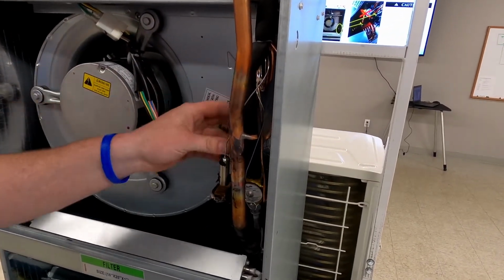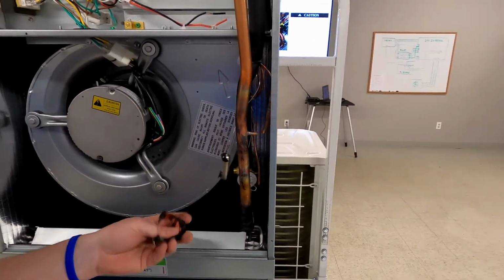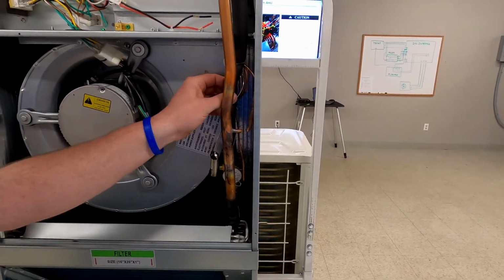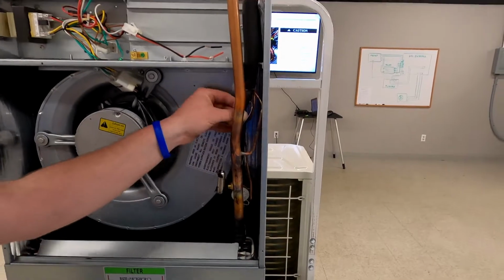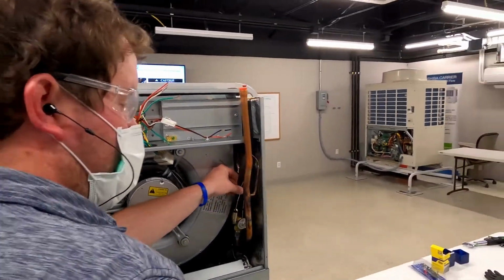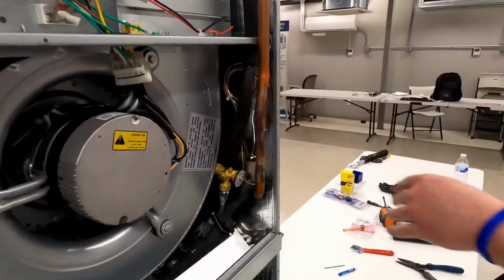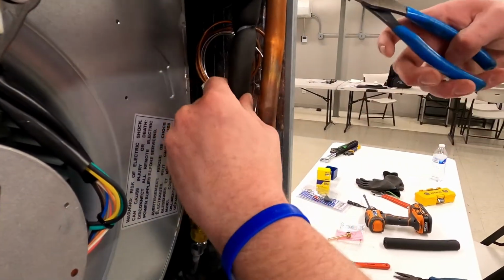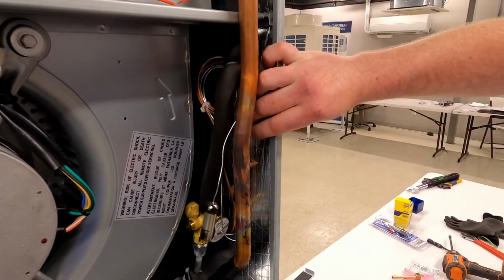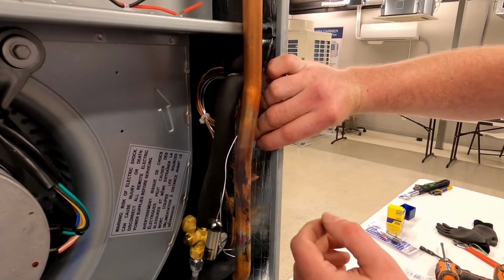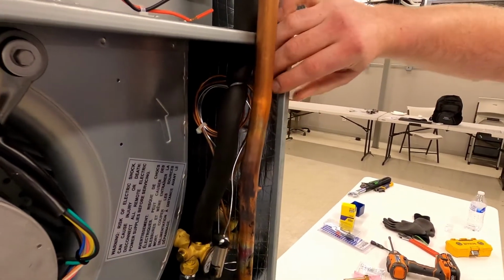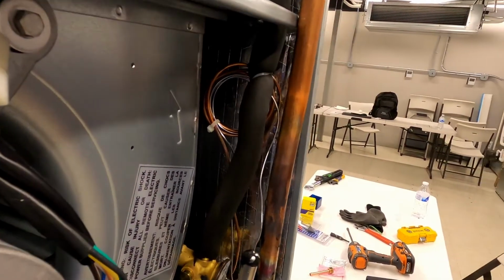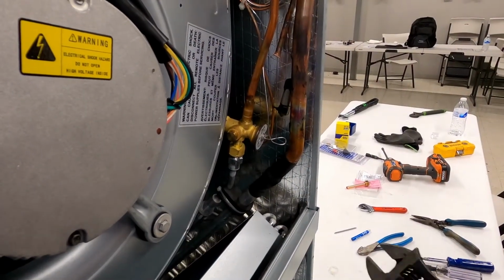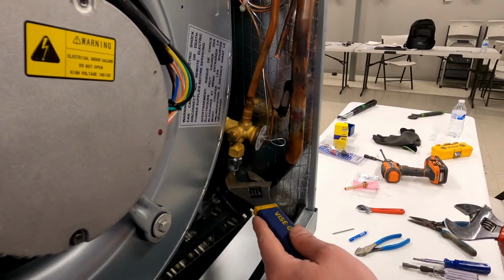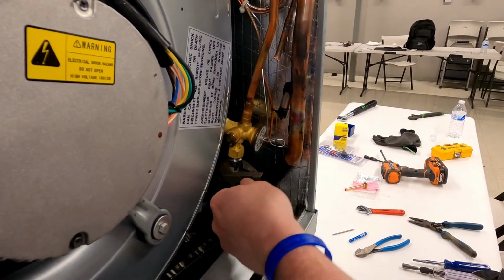Once that's complete, now we're going to move on to removing the insulation from the liquid line so that we can then remove the expansion valve. So now that our equalizer line is cut and pinched, now we're going to work on removing the insulation on our liquid line. Ready. All right, so now that we have the insulation off and everything disconnected, we're ready to remove our TXV.